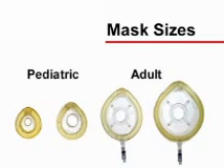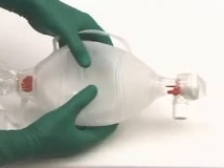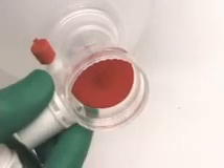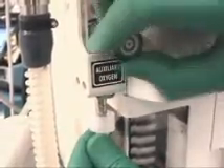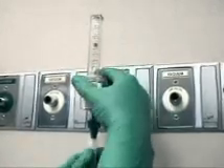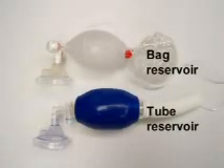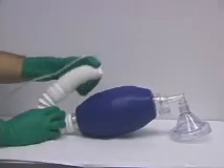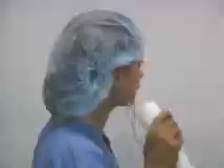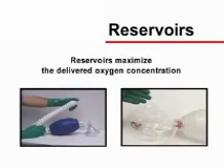Several mask shapes and sizes should be readily available. There are a variety of bag valve designs available. All have a self-inflating bag and a non-rebreathing unidirectional valve, designed to function during both spontaneous and manually controlled ventilation. Because bag valve devices can operate without an oxygen source, it is important to ascertain that supplemental oxygen is flowing when indicated and available. Bag valve devices can be equipped with an oxygen reservoir; if the reservoir bag fills, oxygen is flowing. The purpose of these reservoirs is to maximize the delivered oxygen concentration.